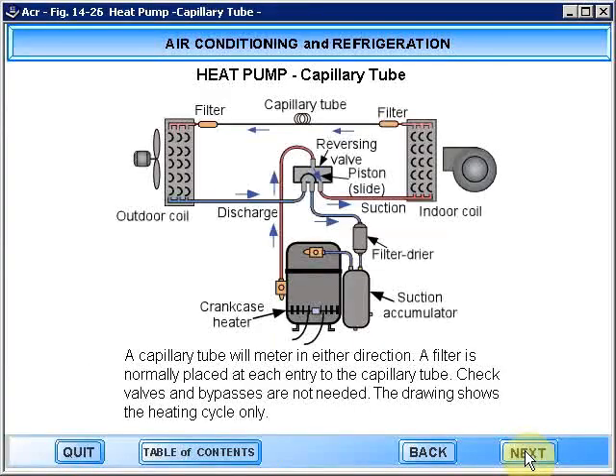A capillary tube will meter in either direction. A filter is normally placed at each entry to the capillary tube. Check valves and bypasses are not needed. The drawing shows the heating cycle only.